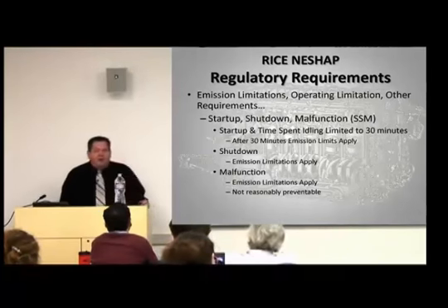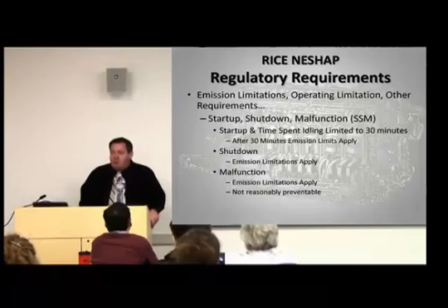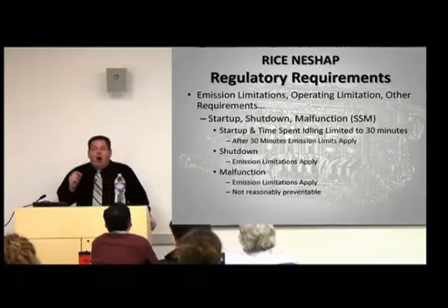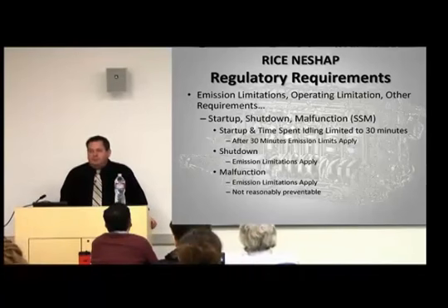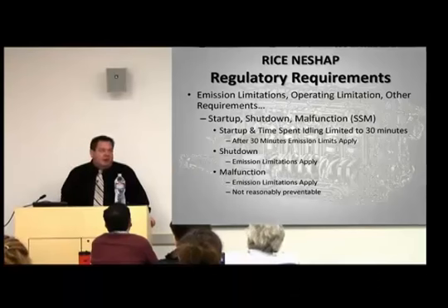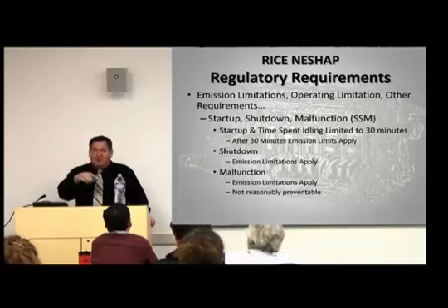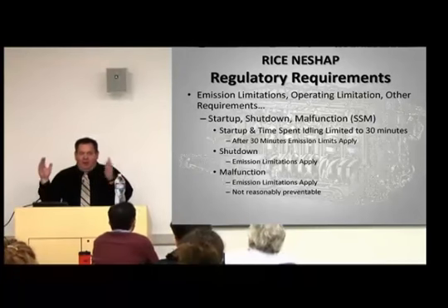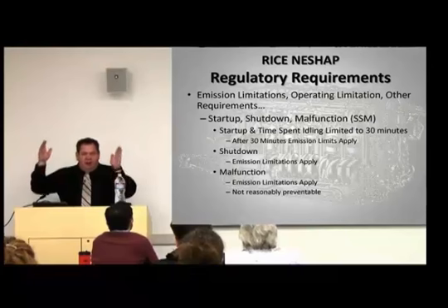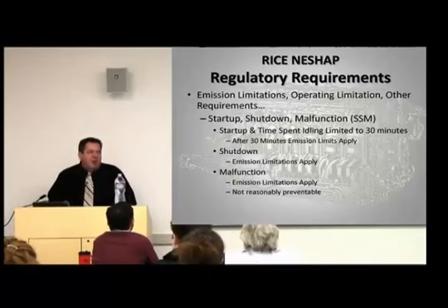Startup, shutdown, and malfunction. These are for engines with numeric emission limitations, and this is what it says. There are no emission limitations during startup. Why? It's typically very dirty anyway. Why is it dirty? One thing, the catalyst isn't warmed up. Catalysts are temperature-dependent animals. While the engine's cold or the exhaust stream is cold, they are just unbelievably big, expensive bricks in the exhaust system that do nothing.